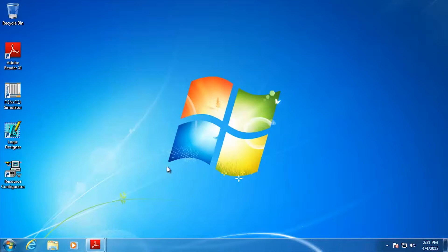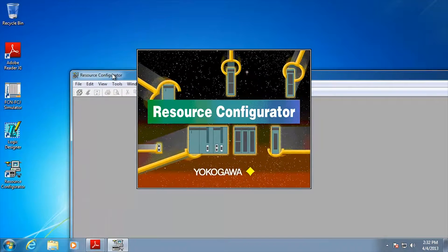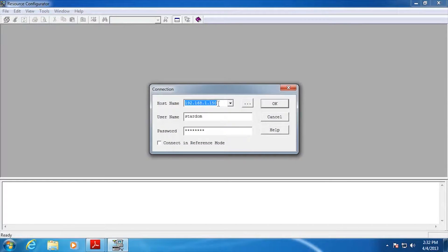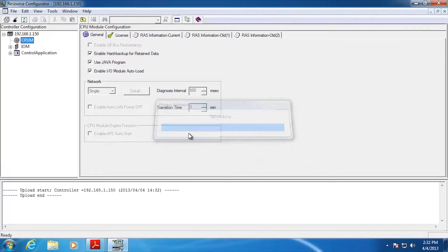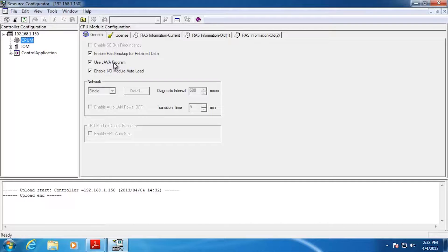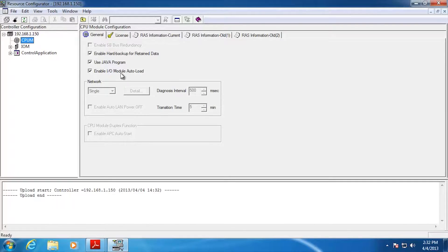I'm going to give you a quick rundown on the stuff that absolutely has to be done or this won't work. Go to the resource configurator and connect up to your Stardom unit using its IP address. The default username is 'stardom' in lowercase and the default password is 'Yokogawa' all in uppercase. The one option you need to make sure is set is 'Use Java Program' — if it's not already checked, check it and click the Download button to push it. If you're using an FCN or FCJ, the system card must have been purchased with a Java license; otherwise you won't be able to run this InfoWell functionality.